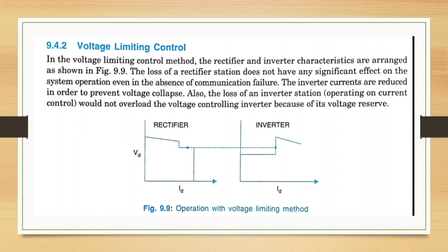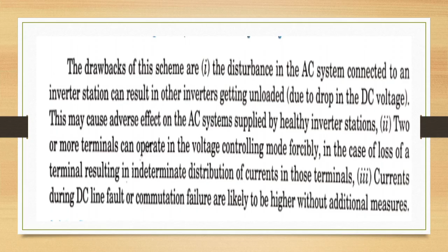Drawbacks of this scheme: first, disturbance in the AC system connected to an inverter station can result in other inverters getting unloaded, and this will cause adverse effect on the AC system supplied by healthy inverter stations. Second, two or more terminals can operate in the voltage controlling mode forcibly in the case of loss of a terminal, resulting in indeterminate distribution of currents in those terminals. Third, currents during DC line fault or commutation failure are likely to be higher without additional measures.